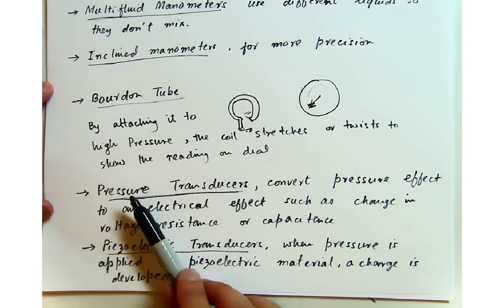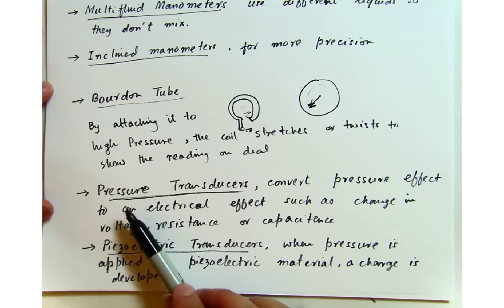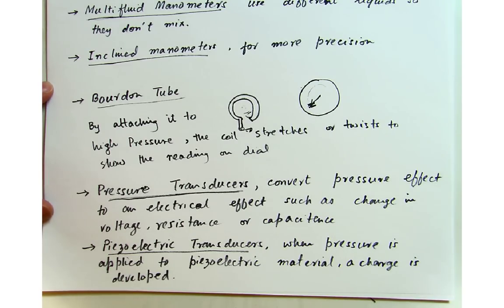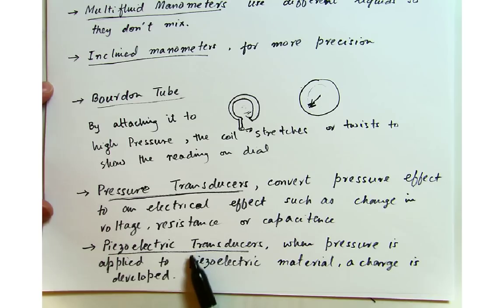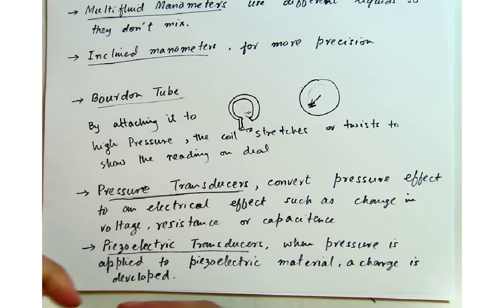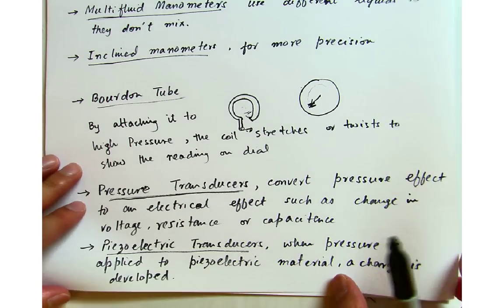Some other devices, which are getting more common these days, are known as pressure transducers. They convert the pressure effect to an electrical effect, such as change in voltage, resistance, or capacitance. Any time you have a change in voltage, resistance, or capacitance, you can simply read it through a voltmeter and it will tell you how much the change was in the pressure. Piezoelectric transducers work when pressure is applied to a piezoelectric material and a charge is developed. Any time something changes in the environment, you can use piezoelectric to measure temperature differences, humidity differences, and so on. The charge can be correlated to changes in the pressure — pretty neat devices.